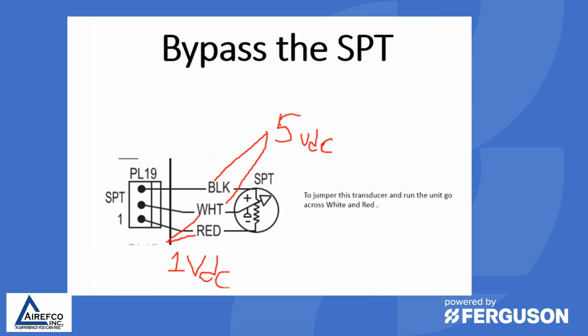Here's a tech tip for you that we have found out in experimenting in the field, that these transducers can be bypassed. If you have a transducer that has failed and you can't get a transducer right away, but you want to keep the people in cooling or heating, you can bypass the suction pressure transducer or the discharge transducer by jumpering the transducer across the white and the red lead. Also, in troubleshooting the transducer, between the black and the white lead, you should have your 5 volts DC, and between the white and the red lead, you should have your feedback voltage of 1 volt DC.